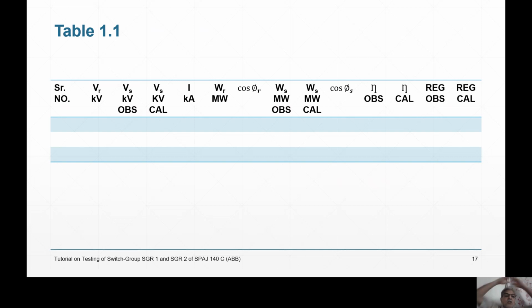And for observing, we'll be taking 2 readings, Vs kV observed and Vs kV calculated also. Calculated means Vs is equal to VR plus Iz. That you can always do. So calculate them and compare them, whether they are more or less equal or not. Similarly, Ws megawatt observed and Ws megawatt calculated. Megawatt observed means whatever the wattmeter reads, and what is calculated? WR, whatever you are reading, plus line losses. Line losses is I square R. R you know, because R you have connected, right? So that you can do. Then you measure cos phi r, right? Cos phi r is there because phi r is available.